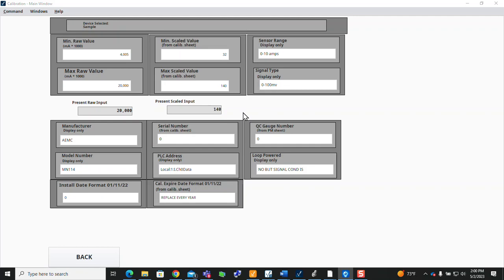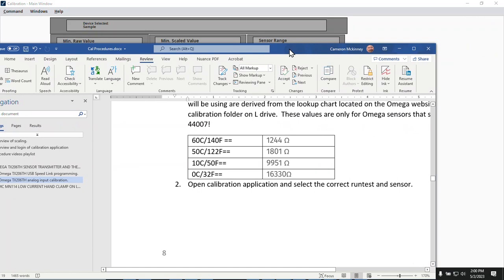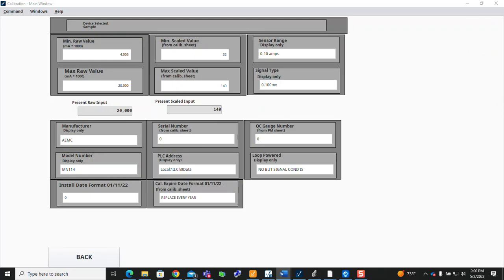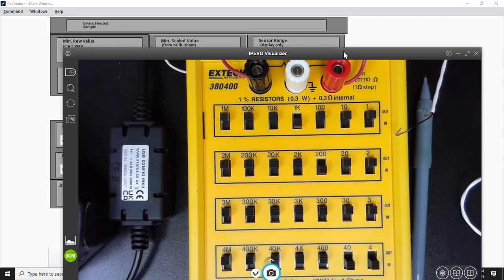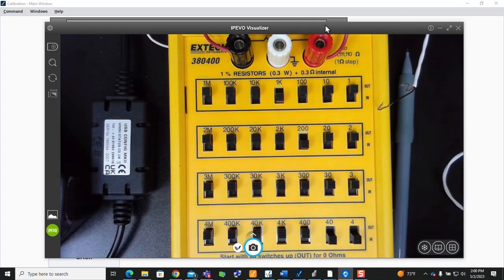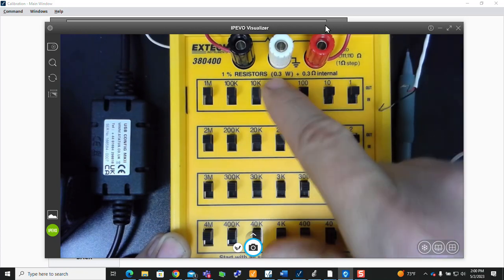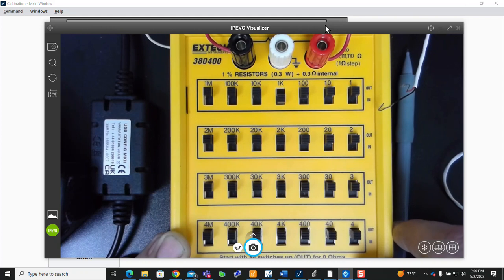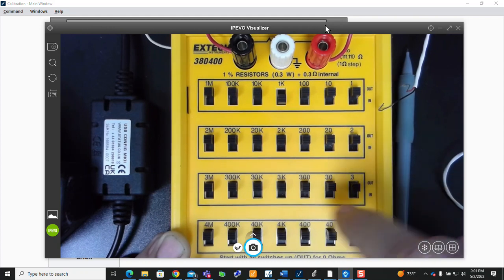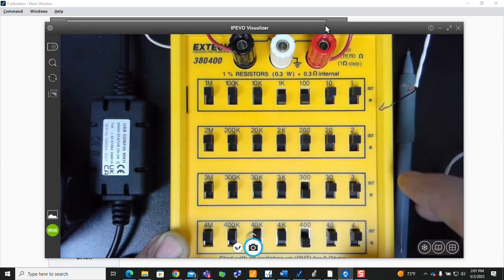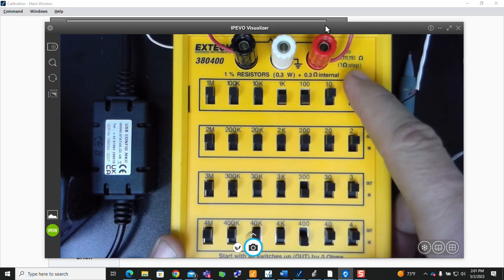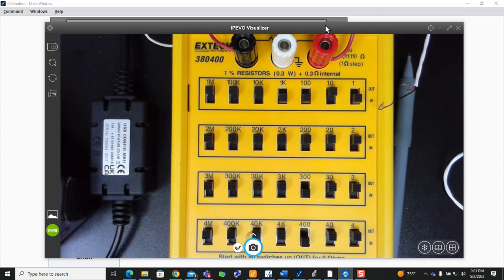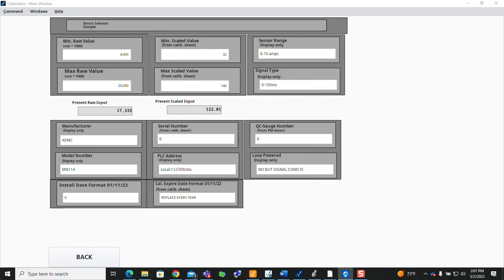Now, I can check the validity or the linearity of this by simply taking one of these other values somewhere in the middle and just punching it in. So if I have a low end, let's just try 1801 and see what we get. We do 1801, we should get 122 degrees Fahrenheit. So I'm going to change my resistance value to 1801 on my decade box. There's 1,000. 400, 700, 800. I think I said 1 ohm, 1801. Yes. And so now we should be displaying 122 degrees Fahrenheit.